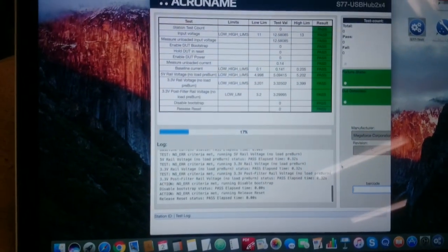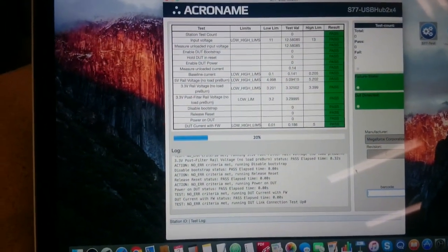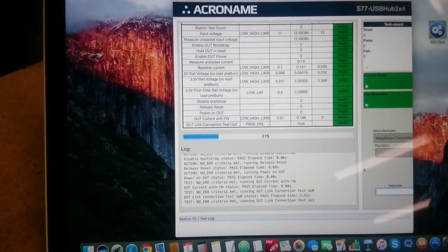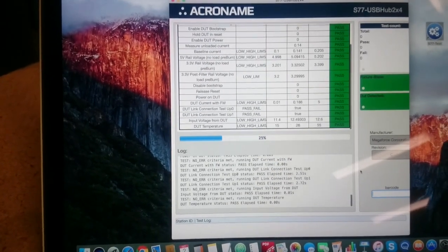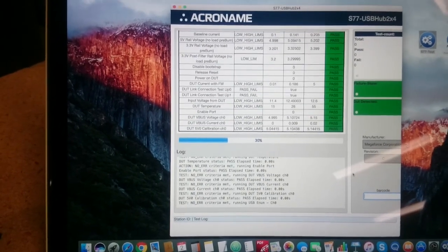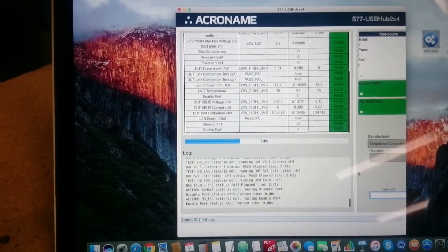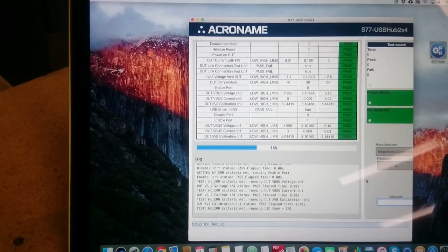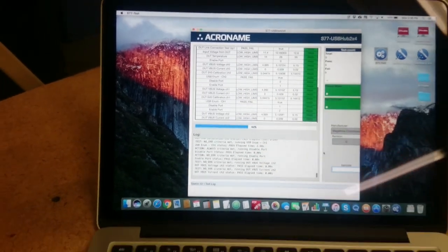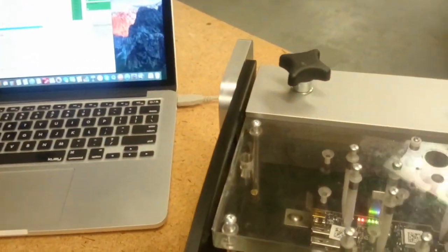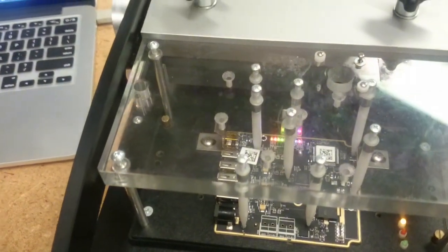This tester will now execute several tests of the DUT. Example tests include checking for overall power shorts, measuring system power rail voltages, measuring DUT power consumption, loading and verifying firmware, electrical LED verification tests, measuring DUT USB power output under load and without load, and verifying communications, along with several other functions, just to name a few.